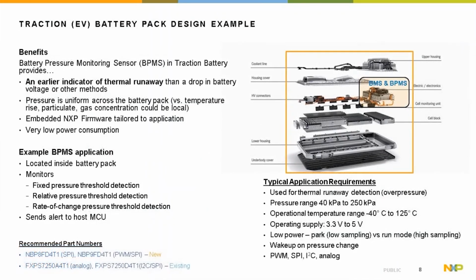Here's an example of an EV battery pack design. The pressure sensor is located in the BMS controller, which manages the battery systems. Here are the typical requirements for the application, which we gathered from talking to dozens of OEMs and tier 1s. The pressure range is from 40 to 250 kPa. The temperature range is -40 to 125 degrees C. The operating supply voltage is from 3.3 to 5 volts.